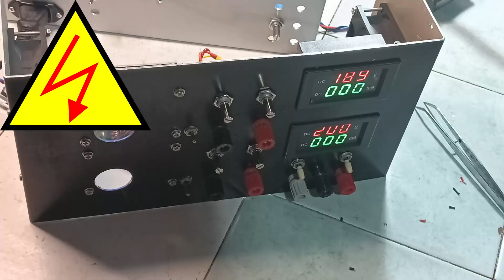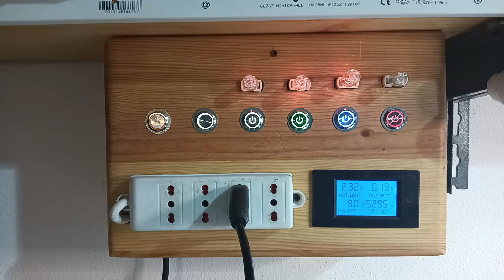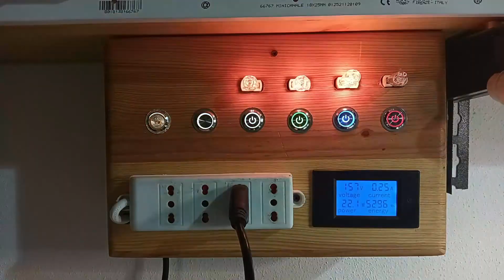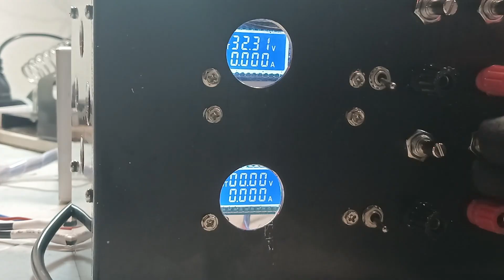The unit is turned on using a dim bulb tester, and it is observed that the current drawn by the high voltage module is intermittent when it is set for relatively high voltages. The low voltage modules seem to be working correctly as expected.